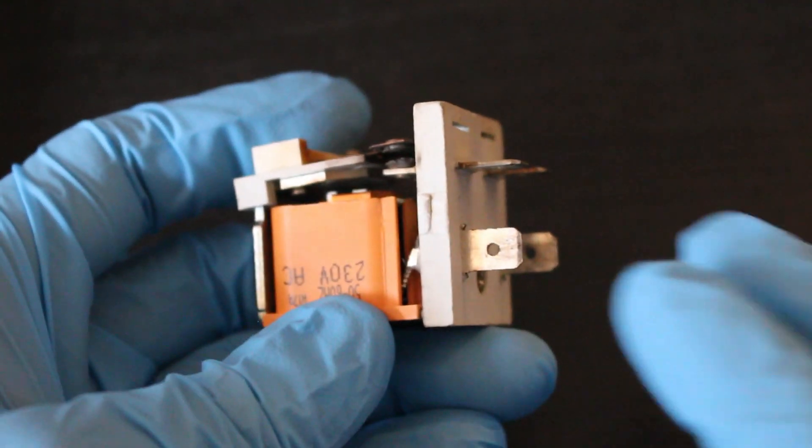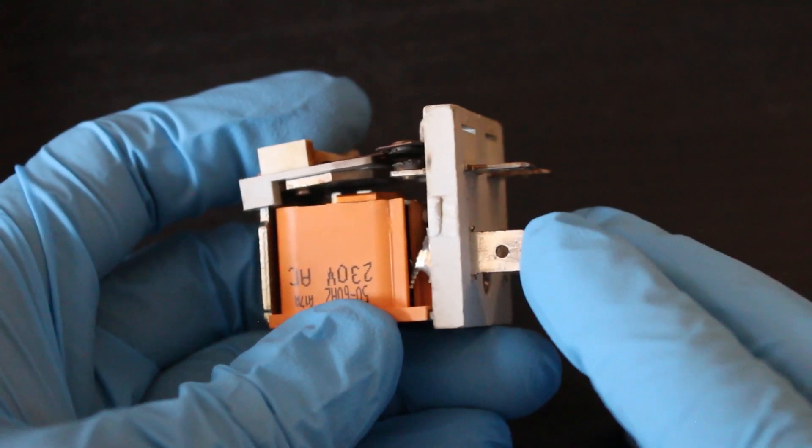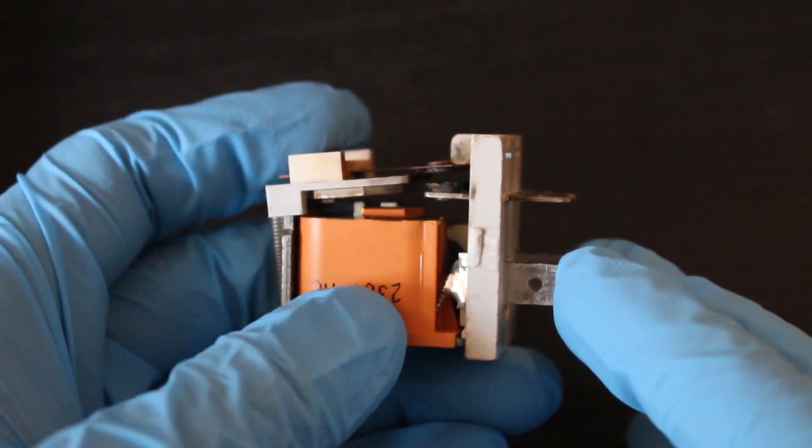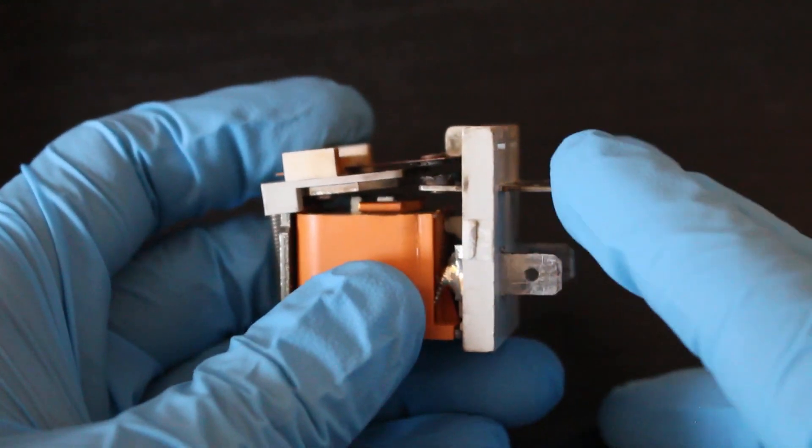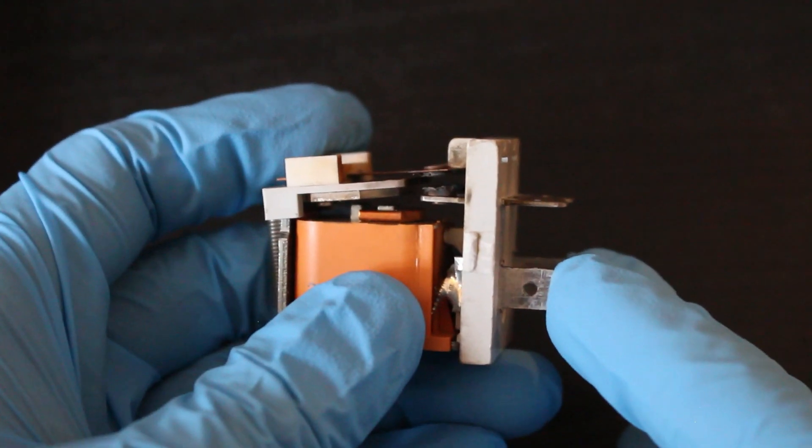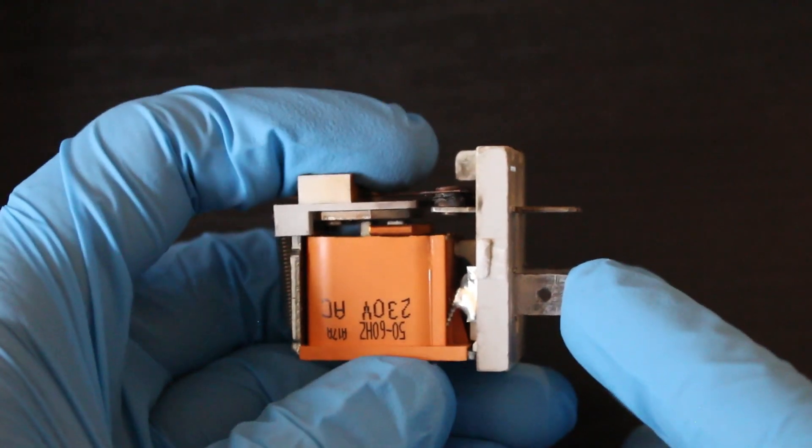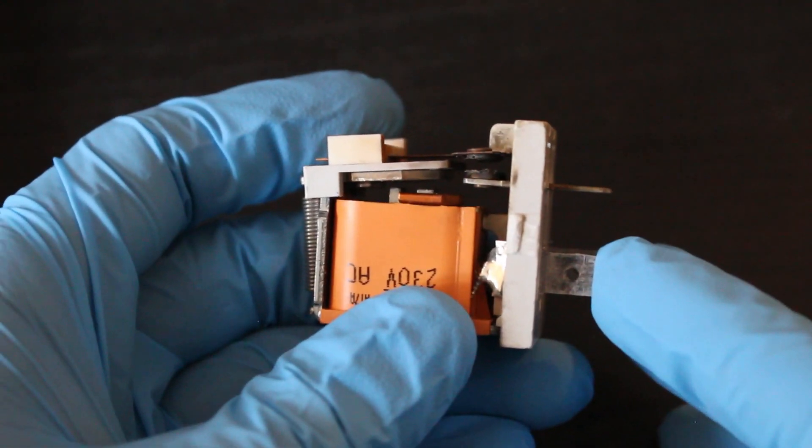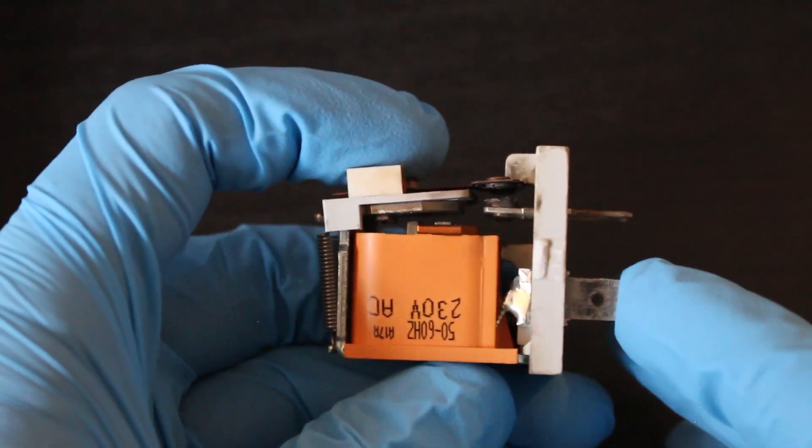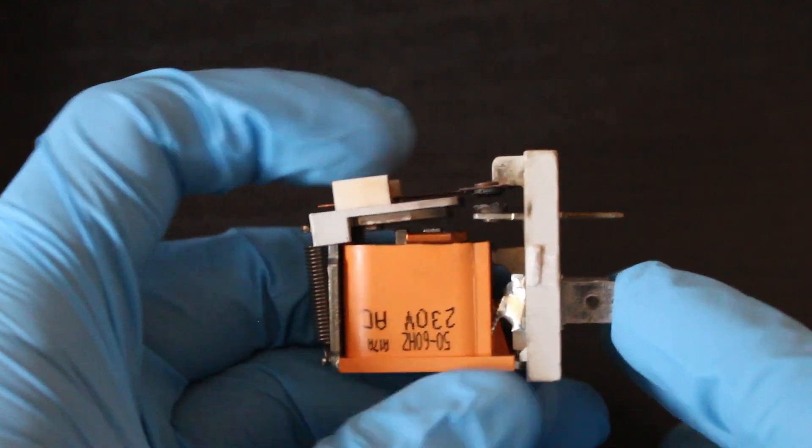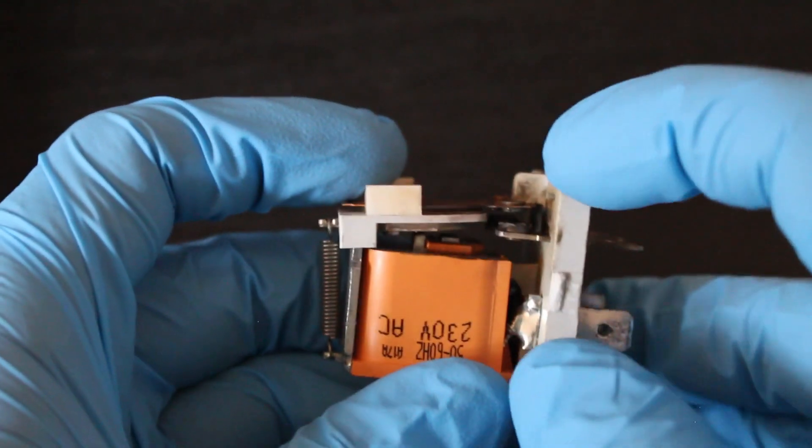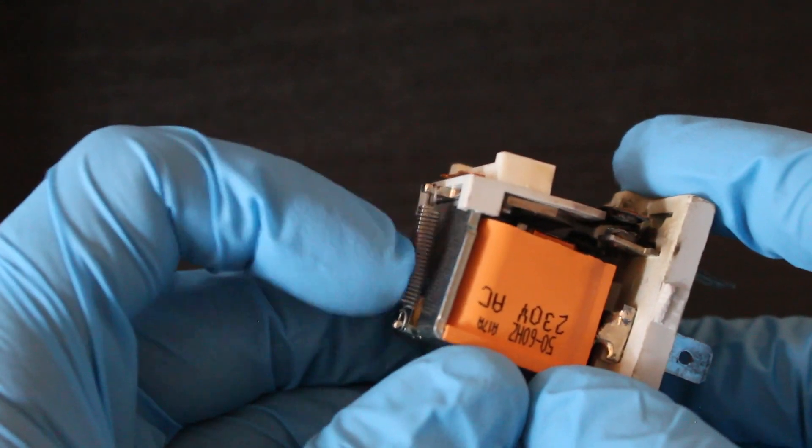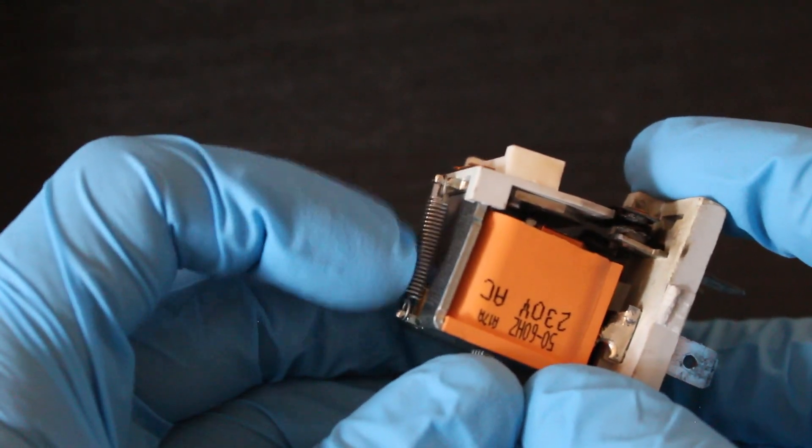The way this operates is when current flows through the coil, a magnetic field is developed around the core. Keep in mind that the set of contacts and the coil are electrically isolated. They're just wound around the same core. So when current flows through this coil, an armature - this piece right here - will close and either open or close a set of contacts when the magnetic field overcomes the strength of this spring.